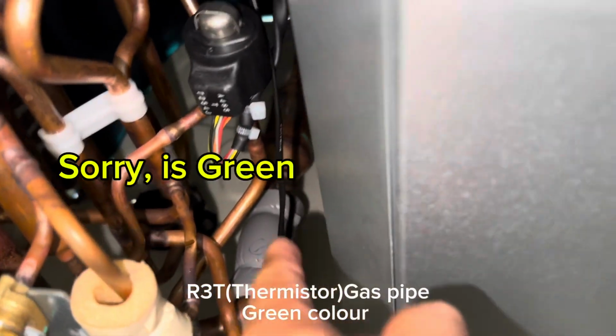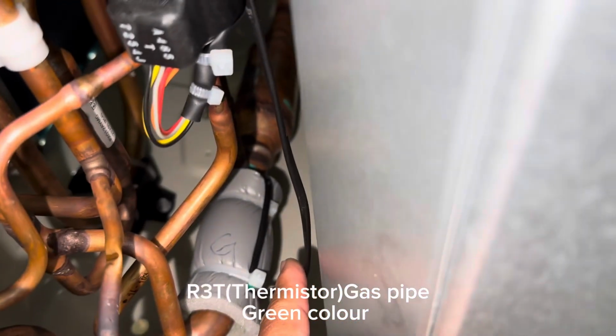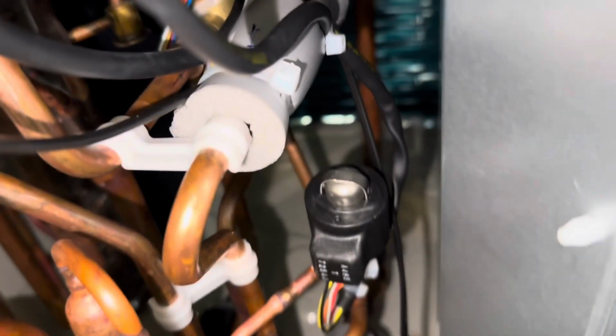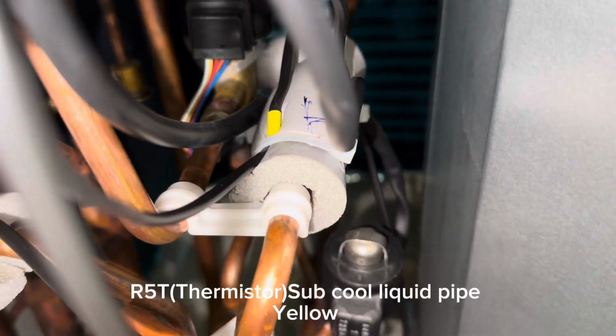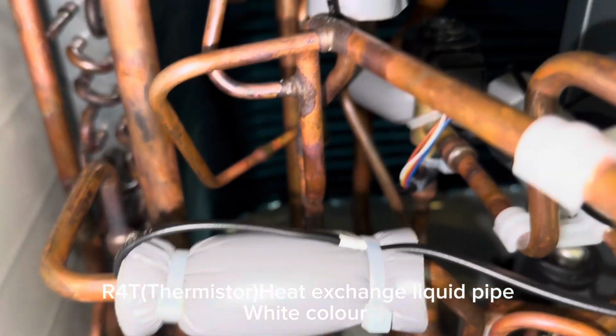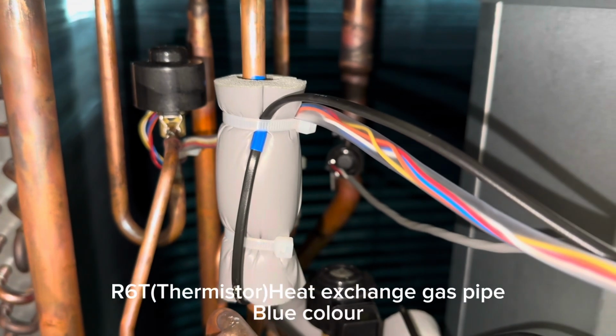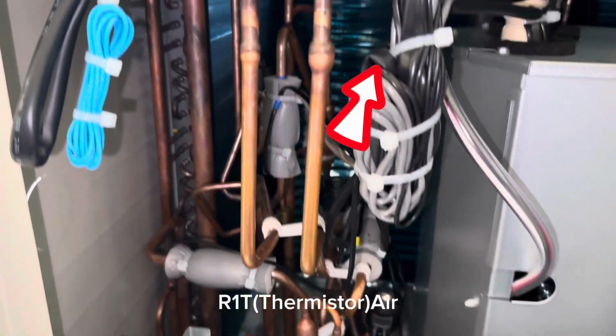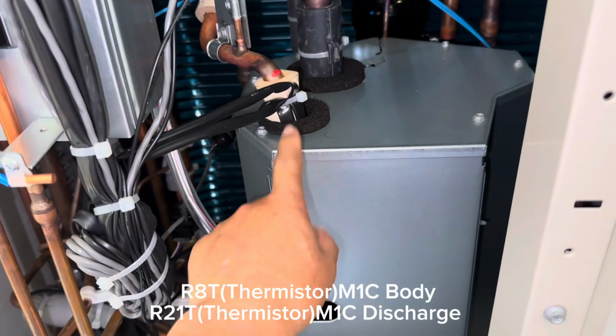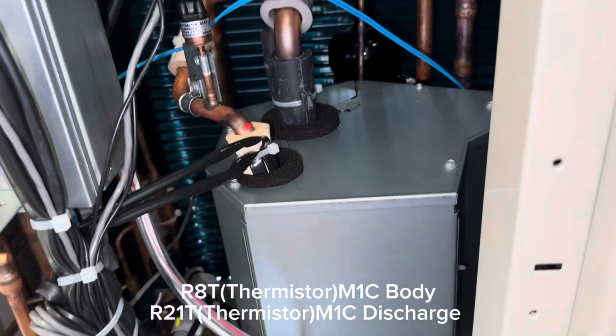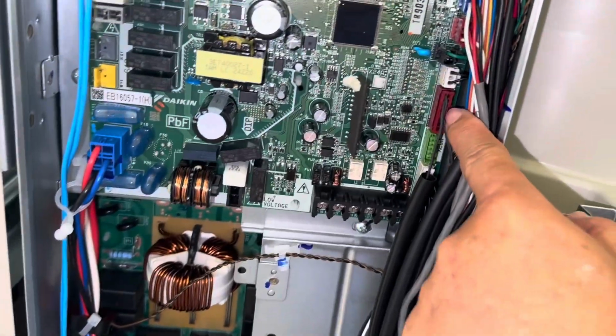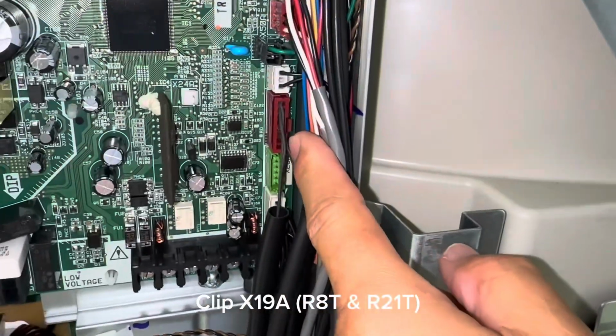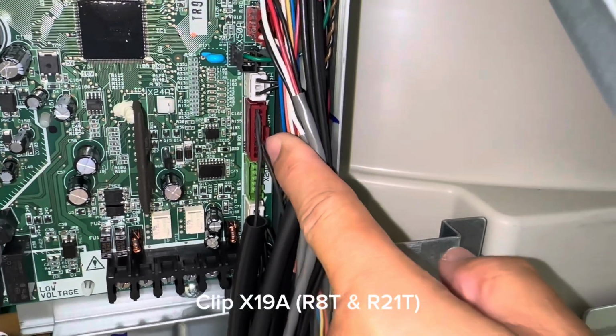Okay, at the bottom, this is the gas pipe thermistor, blue color. Yellow, white, and blue. Okay, total got four thermistors inside the component. One is a discharge thermistor, another one is compressor body thermistor. The clip is red color, X19A, thermistor R21T and R8T.